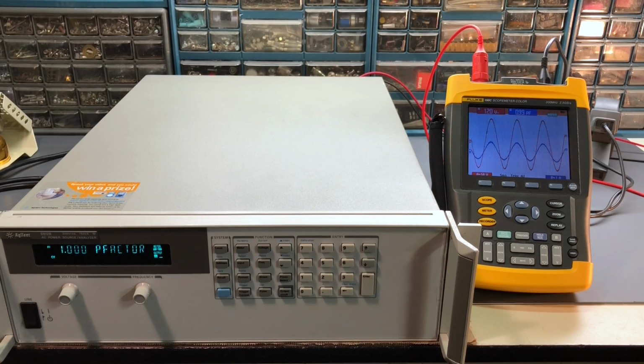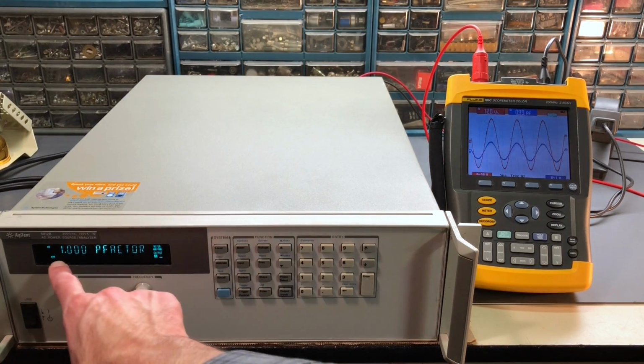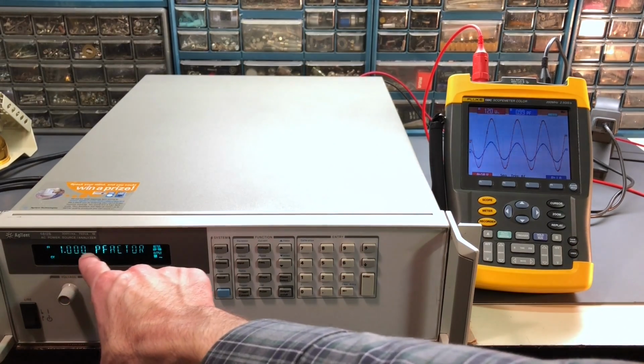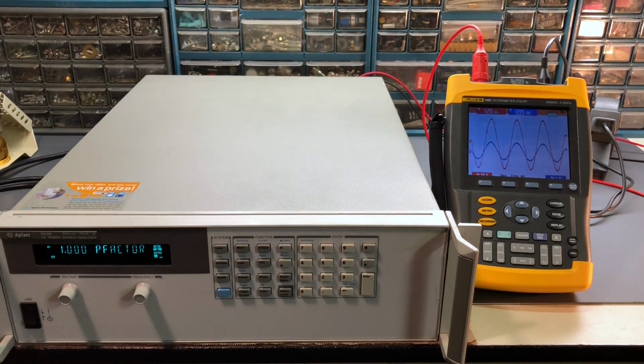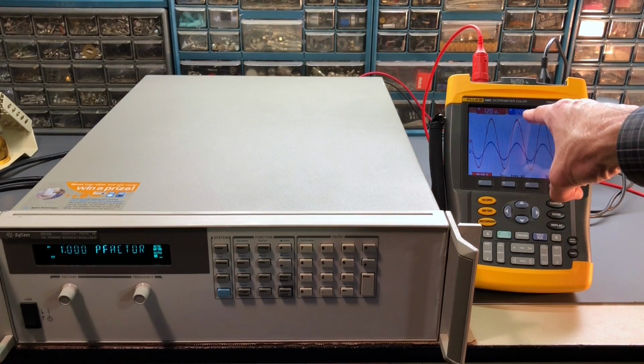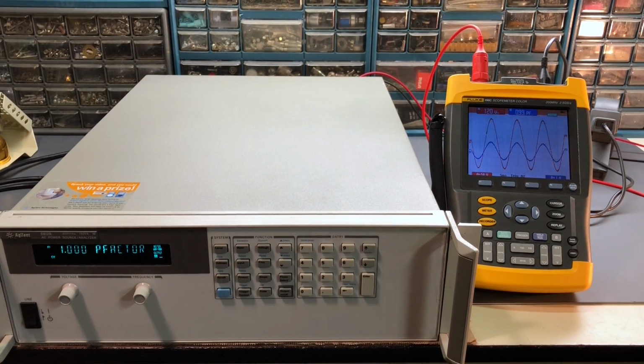Alright, here's checking the power factor reading, again with the incandescent bulb. A resistive load should be 100%, or a power factor of 1, and we do have that. So you can see over here it's indicating 1 point and then all zeros, so 100% power factor, and over here also it's 0.99, so right at 1. So everything's in agreement there, looks very good.